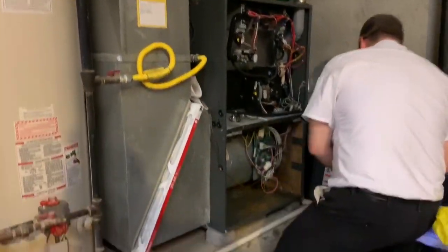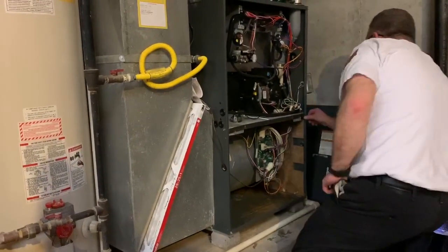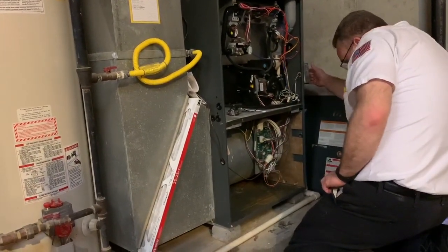The negatives: they waste more water. I always learned that it's four parts water to one part humidity, so quite a bit of waste gets flushed through these things and not really used as actual humidity. They're also dependent on the blower in your heating system — they can't put humidity into the air on their own. They need the heating system to be operating at the same time to blow the air across the water panel inside, so they're dependent on the heating operation, or at least fan movement.